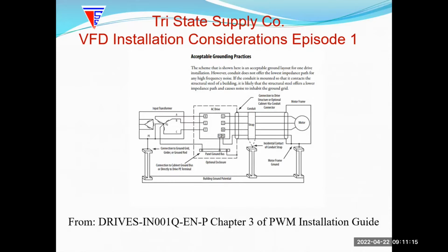But in this typical installation, a lot of times you're going to run a conduit, okay? And conduit touches ground in many points, especially where you're strapping it down. And conduit, being a metal substance and thin, the high frequency noise that the PWM carrier frequency generates on the drive is going to conduct onto this conduit. And if you're not careful, it could actually find a better path back to the drive through the ground plane and back this way. And that's what we're trying to avoid.